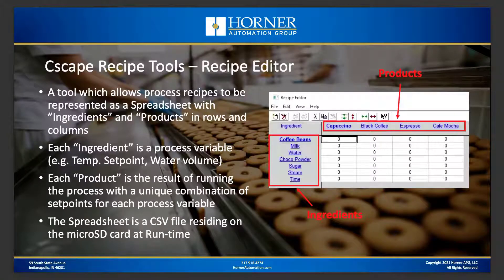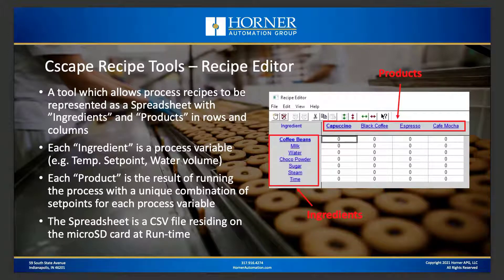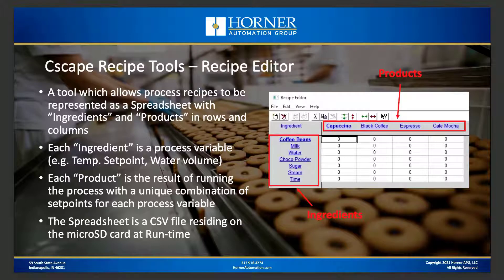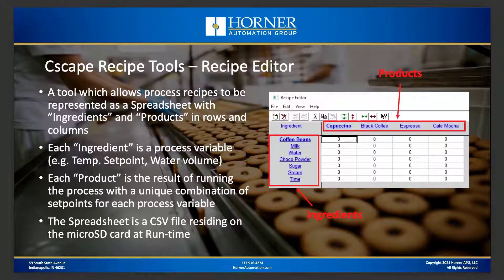Let's dive into those Cscape recipe tools, starting with the recipe editor — really the main tool Cscape uses for handling recipes. It allows Cscape and the OCS at runtime to handle recipes as ingredients and products in rows and columns on a spreadsheet. Think of every ingredient as a process variable — a temperature setpoint, water volume, pressure, whatever the case may be. Each product is the result of running your process with a unique combination of setpoints for each process variable managed by the recipe function. That spreadsheet is a CSV formatted file that resides on the micro SD card, so the OCS retrieves all process parameter setpoints from that CSV file on the memory card.